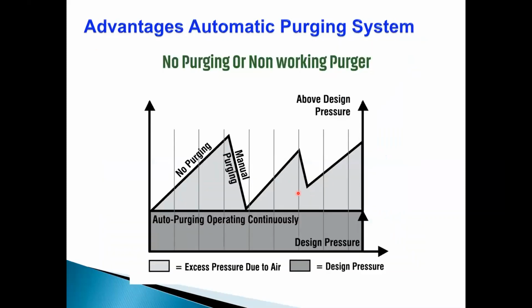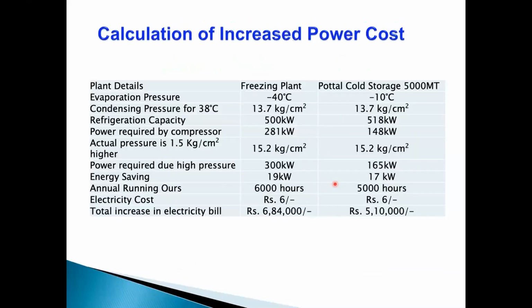But what we have here is that if there is manual purging happening, when there is no purging, your pressure is rising. With manual purging, the pressure will drop down. Then again, when there is no purging, your pressure will rise, and when it is purging, it drops down. So this becomes a cycle, and you spend this energy every time you are not purging. Whereas auto purging will maintain a constant design pressure, and there's no excess pressure. So you're operating at a lower condensing temperature. You have higher energy efficiency.